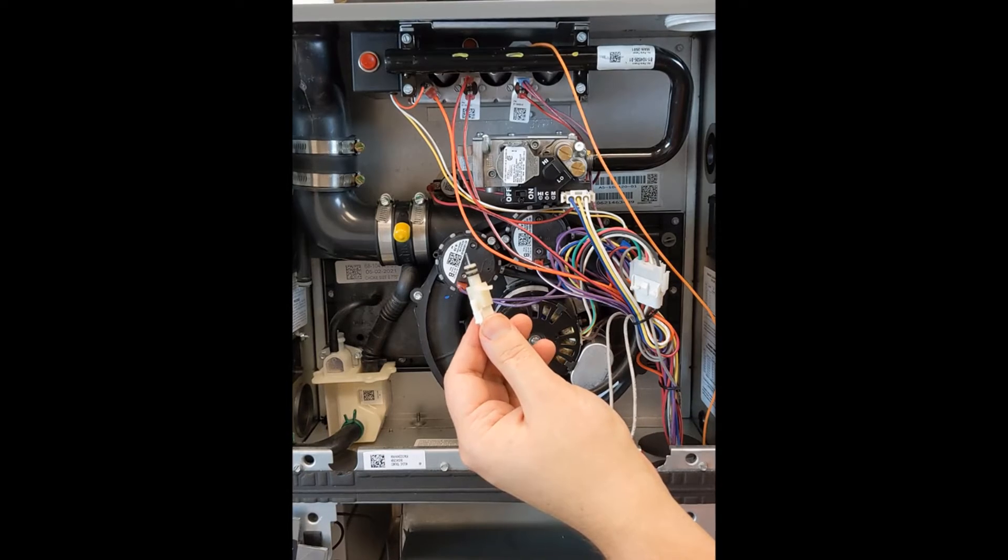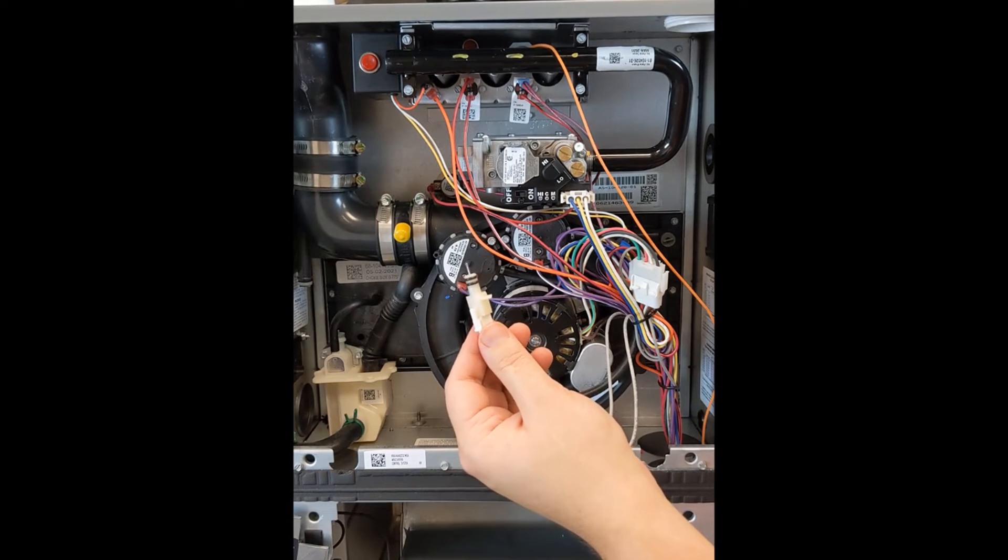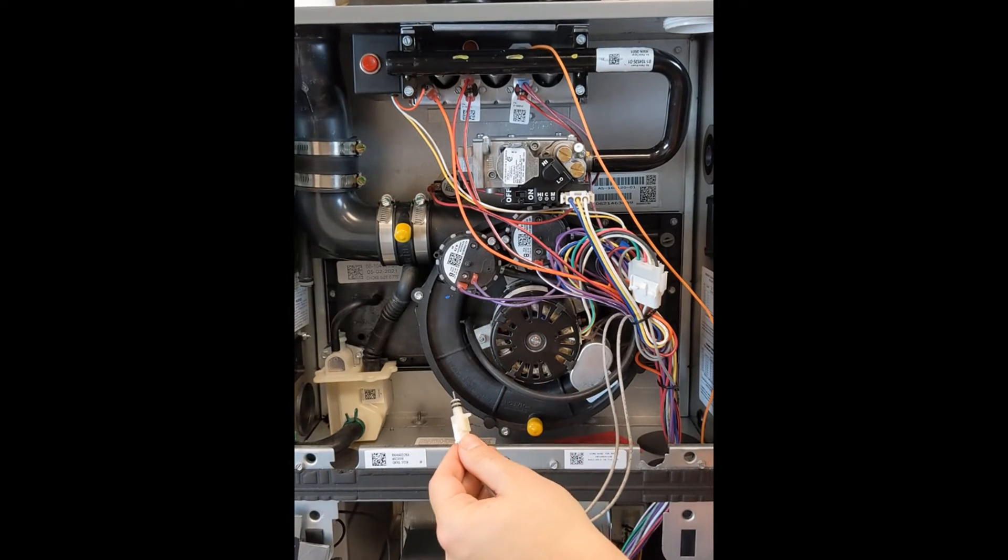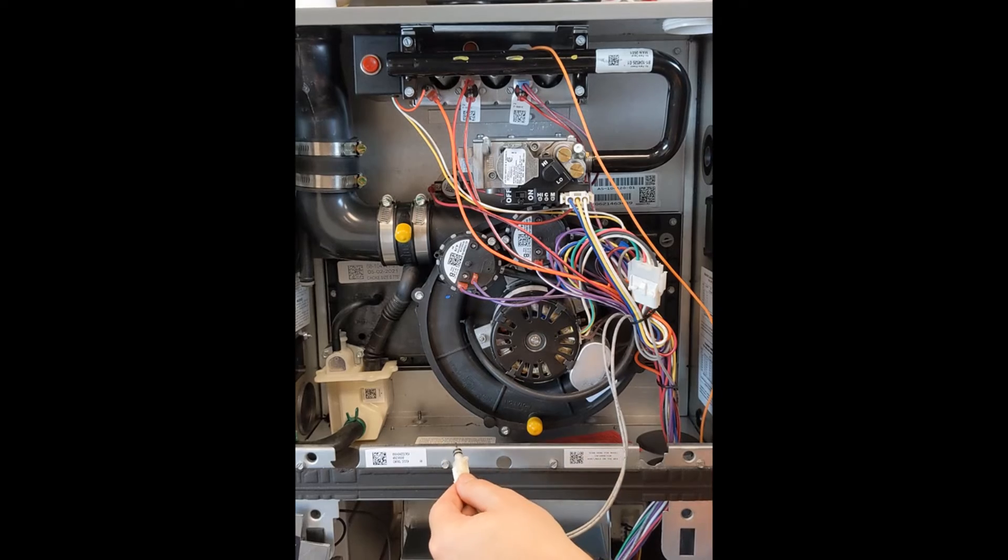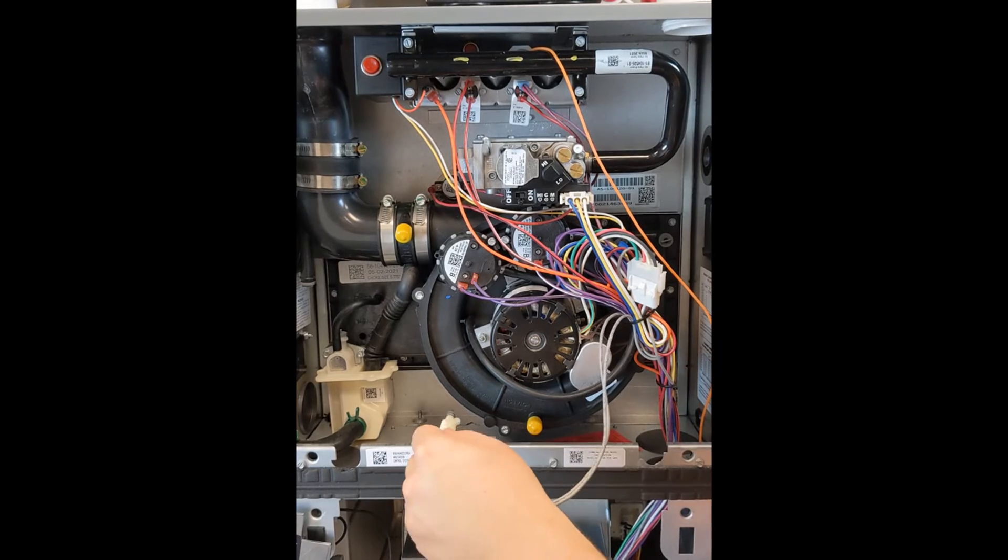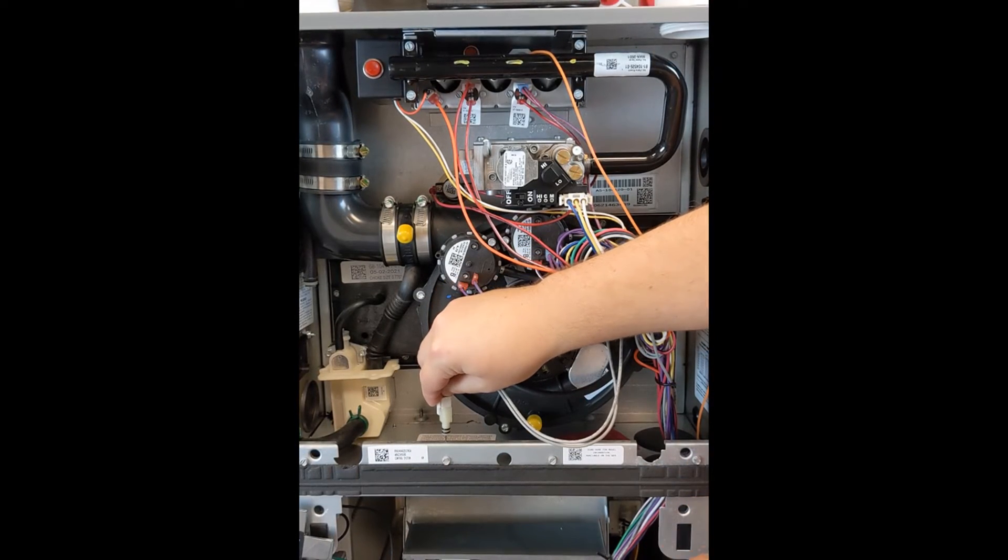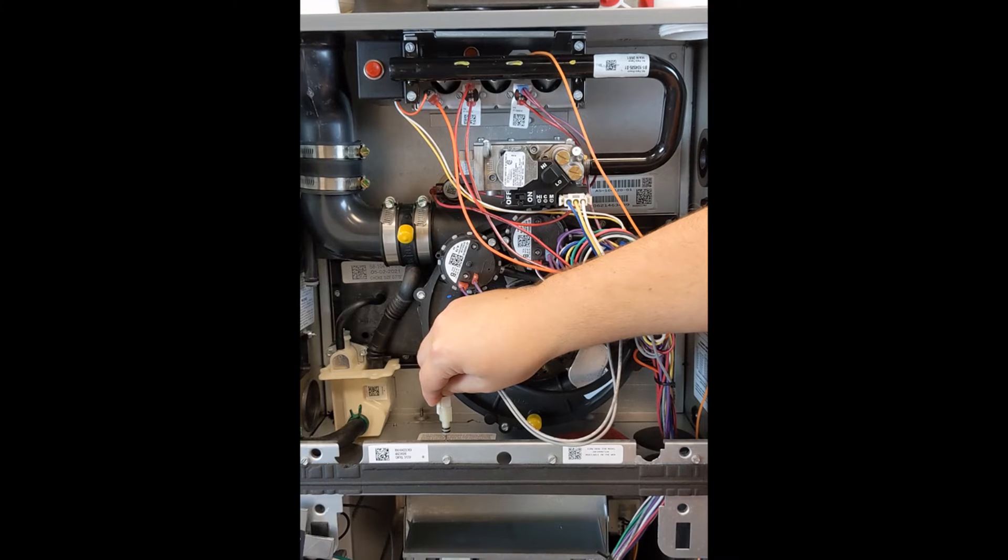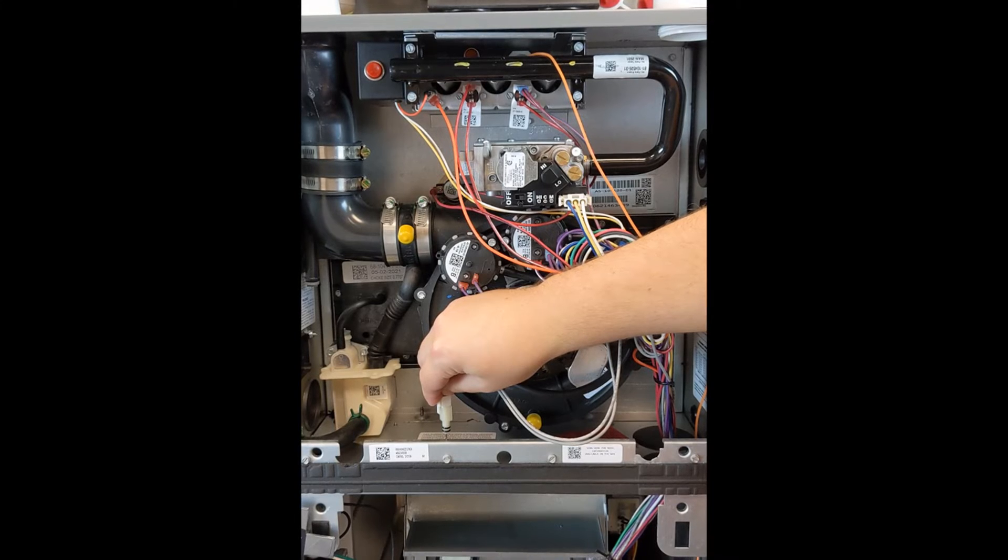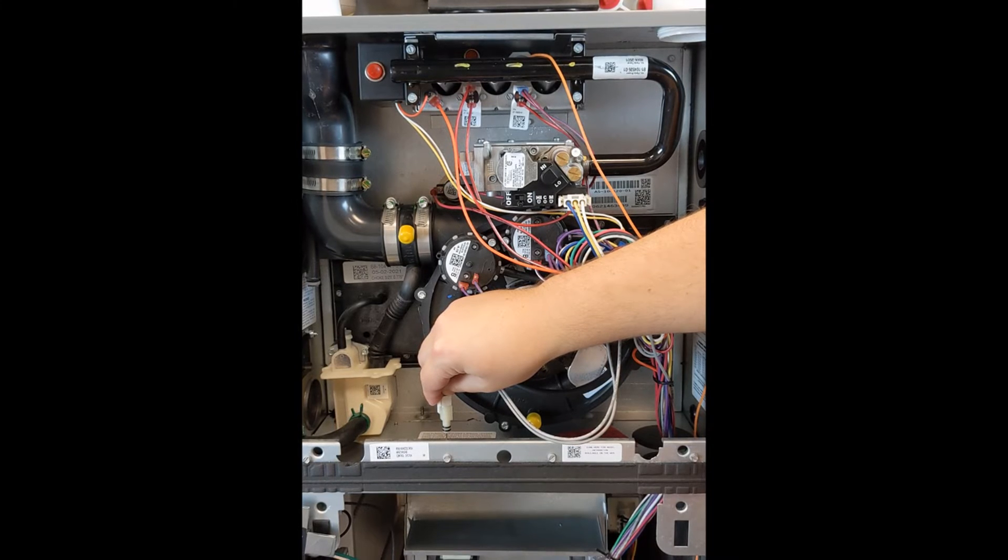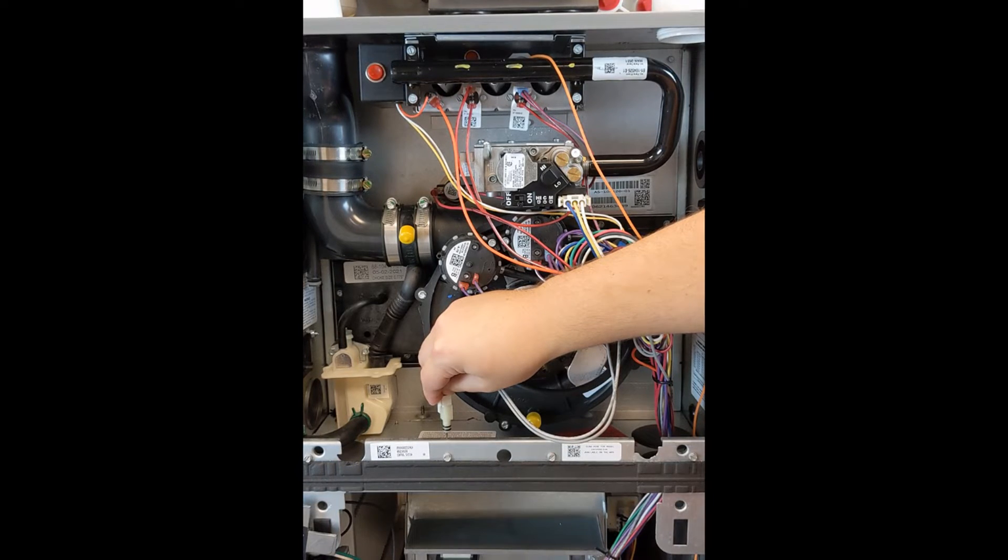If they're clean, simply then, during call for heat, short out the water sensor to ground, and you should see a water sensed code.